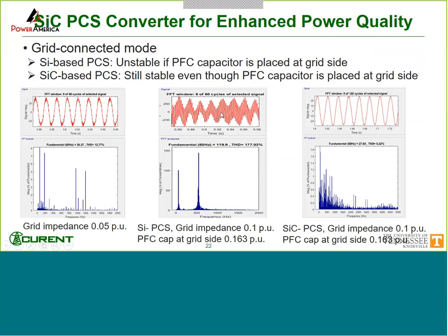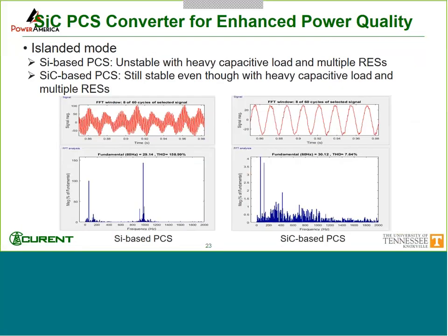So here is a comparison of the silicon-based case and the silicon carbide-based case. One is switching at 1 kilohertz, the other is switching at 10 kilohertz, with exactly the same load condition. This is grid connected mode, and the load is on the grid side. You can see in one case, you could have the resonance. For the other case, the resonance disappears because of the higher control bandwidth available for silicon carbide. And this, of course, is for a fairly weak grid condition, about 10% impedance.